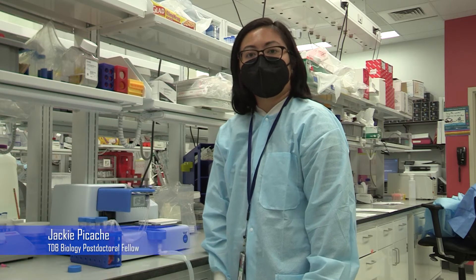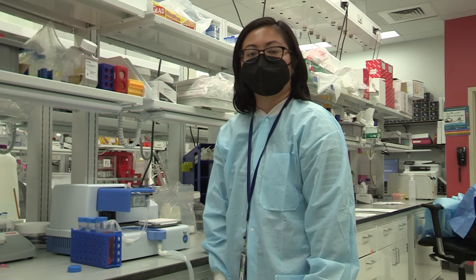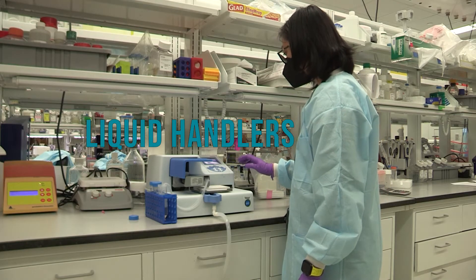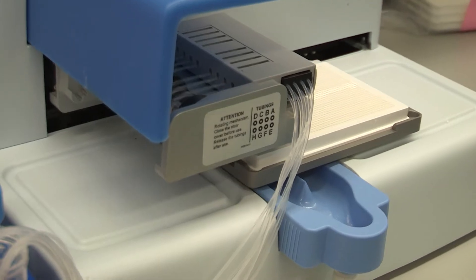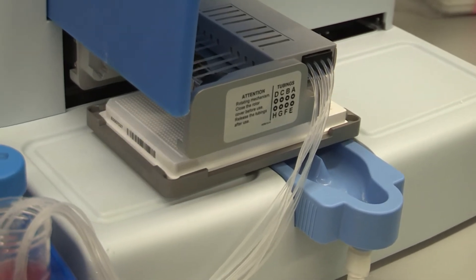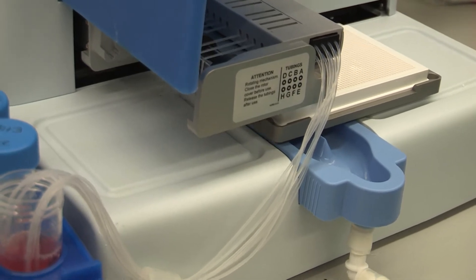Our lab relies heavily on miniaturized assays using 384 and 1536 well plates. Therefore, we rely heavily on the MultiDrop and other liquid handlers to dispense cells and reagents accurately. The MultiDrop is our workhorse cell dispensing mechanism that has an 8-tip dispensing powered by a peristaltic pump. It is able to fill a 1536 well plate in less than a minute.